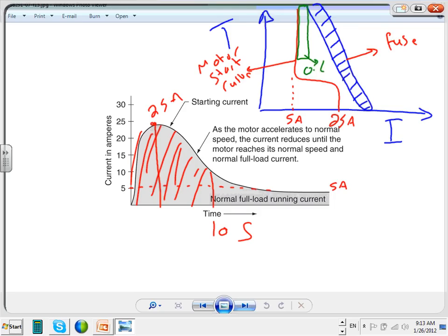It will give it 10 seconds, up to 10 seconds. Can you guys see here? It says 10 seconds. So, Nick, you are a motor, you have 10 seconds to come up to speed and suck 5 times more current, only 10 seconds. If you continue to do that, continue means the time going up, what's going to happen to this when it goes up? The fuse is going to be hit. When you hit the fuse, it will open.